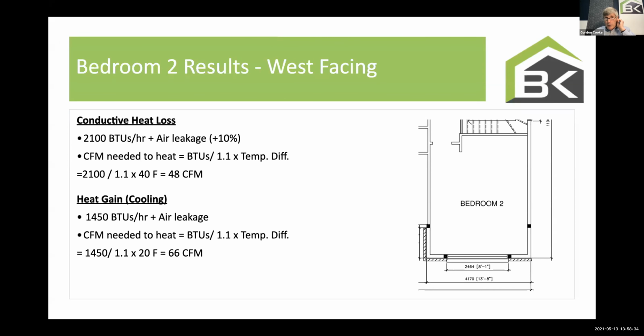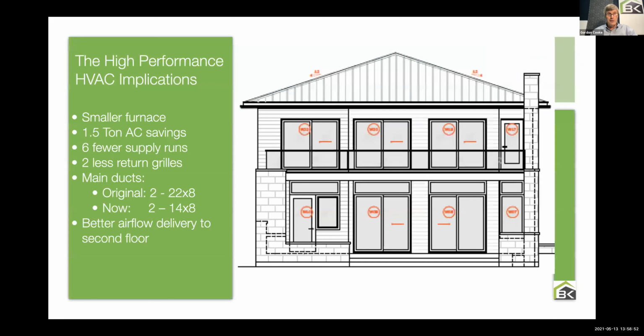But I would say homeowners haven't been told that. Your homeowners have not been told that this system was set up for both heating and cooling, and heating and cooling is different. So you're going to have to balance it. And if they go, well, that's not me, somebody else has to do that, then you'd say, fine. Then I'll sell you a zoning system or something different to get you different performance out of that.